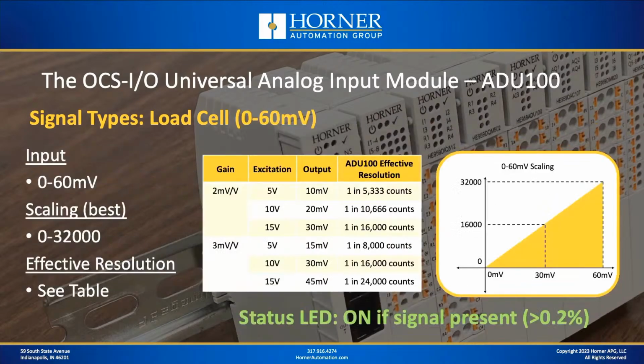Now let's talk about the way that values are reported back and also talk about something that I'm calling effective resolution. So if you're using a load cell range with an ADU100, you're going to select the 0 to 32,000 scaling range, even though some lower resolution ranges are available. That's just because that's the only real practical range available. And 0 millivolts represents 0 counts, and 60 millivolts is represented by 32,000 counts.